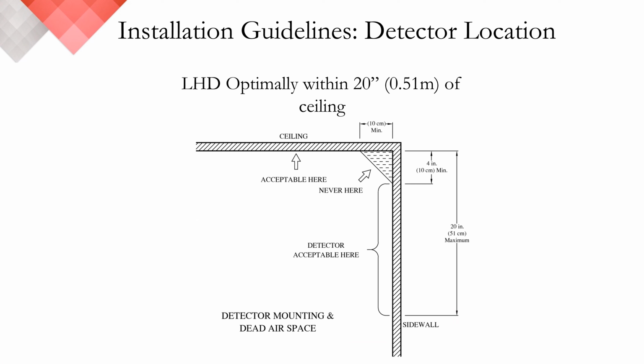When it comes to the physical location of the detector, the space it occupies and the area it will be installed will dictate where it can be positioned. From there, we follow the guidelines we're going to cover based on the shape, style, and as we discussed before, the height of the ceiling. Heat from a fire rises to the ceiling in a plume and spreads radially from the fire source. As the hot gas is cooled, they begin to bank down from the ceiling.